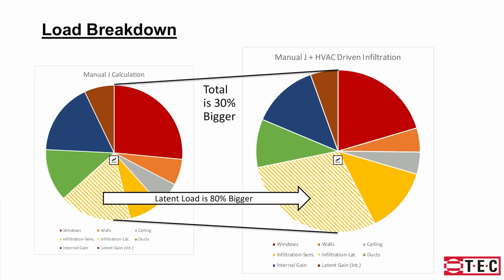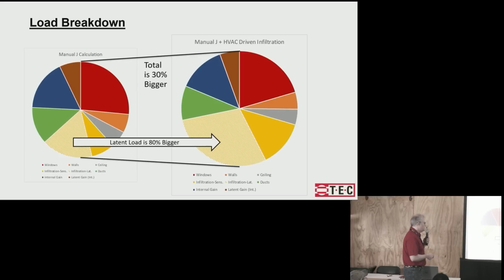And I've broken it up into the sensible load in the solid yellow, and the striped yellow is the latent load. And what we're seeing here is that this wedge in the pie now becomes almost half of the load. It's infiltration now because of those additional 300-ish CFM that's coming in. Okay, so this explains what we're seeing. This is a closer look at what's going on.